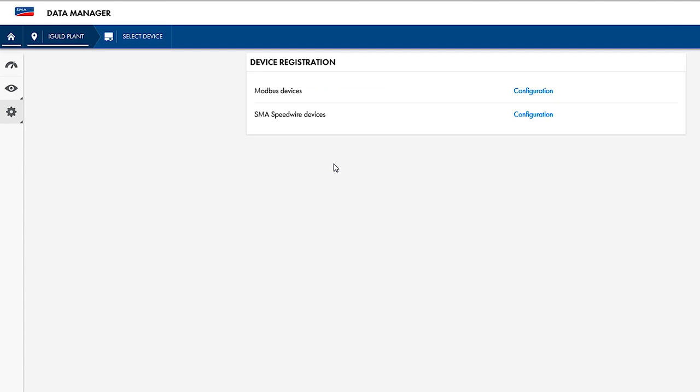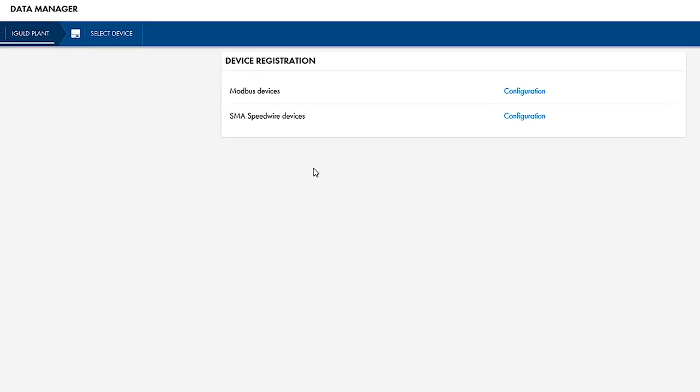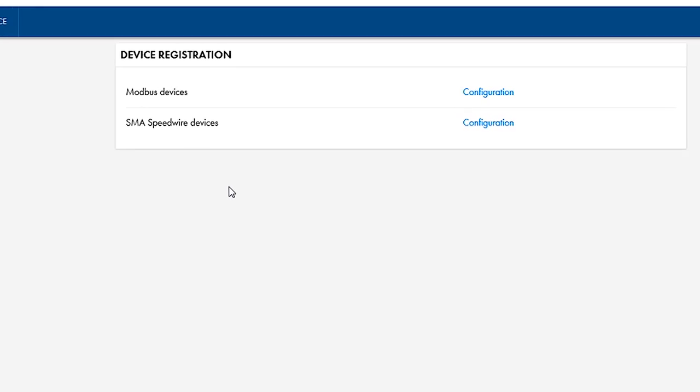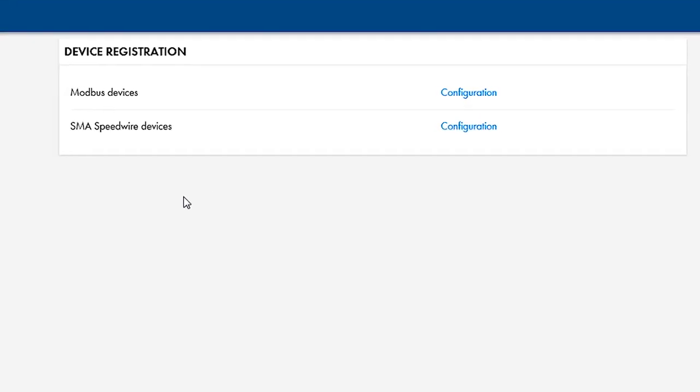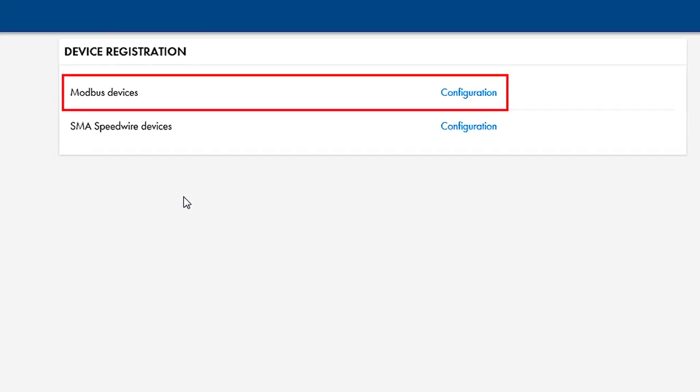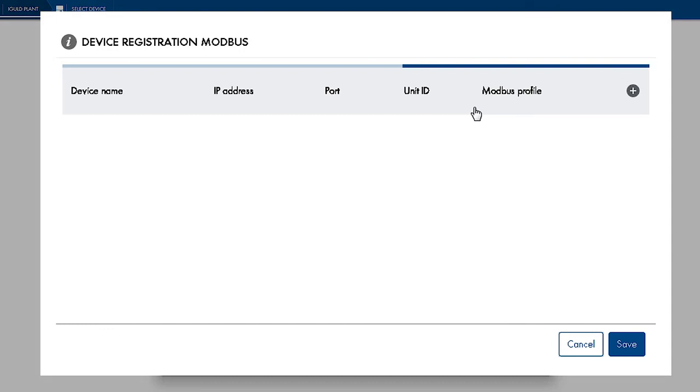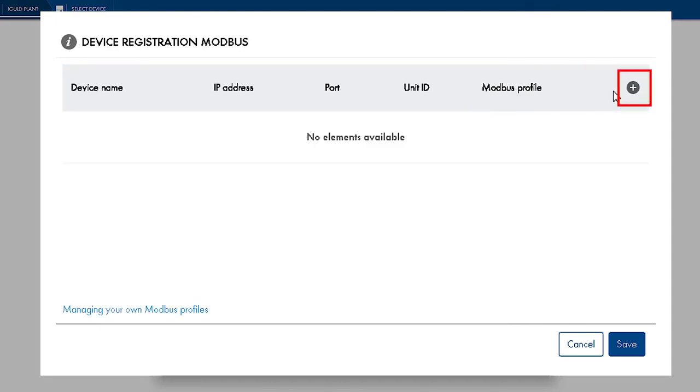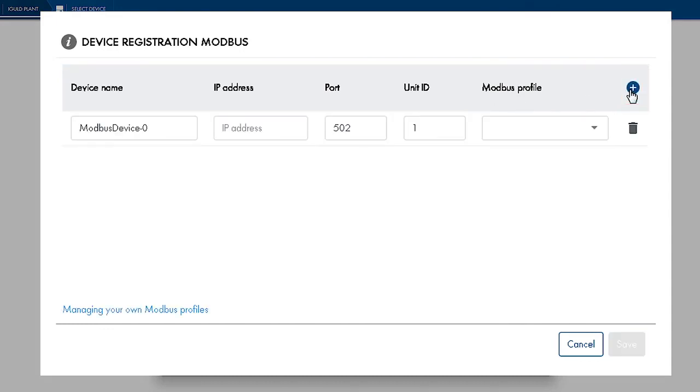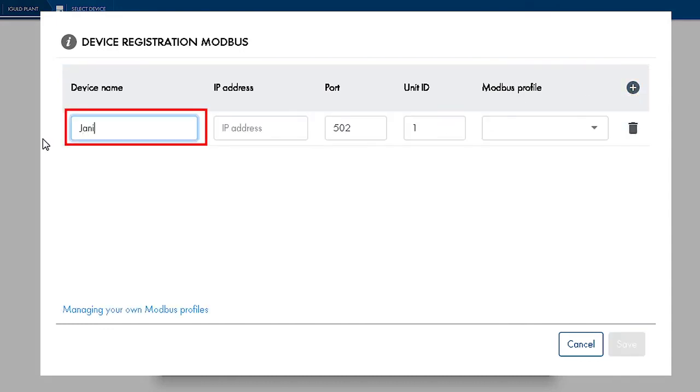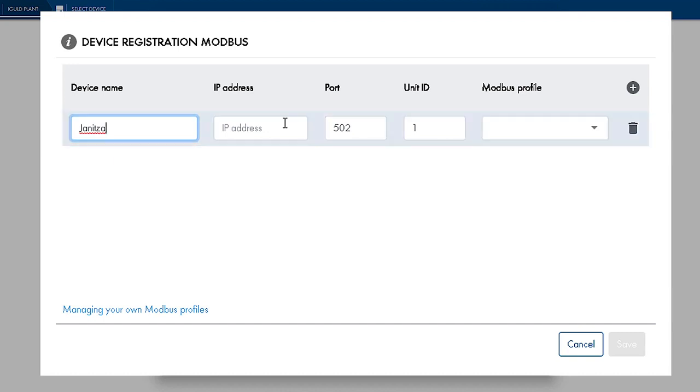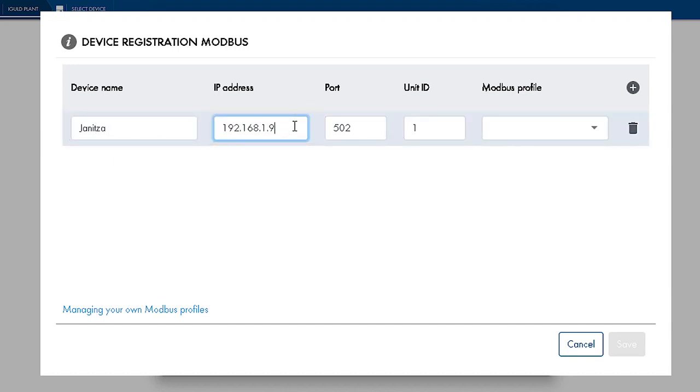A Janitza UMG604 Modbus energy meter can also be set up via the Device Registration menu. To do so, click on Modbus Devices Configuration. Then assign a device name and enter the IP address, port, normally 502, and Unit ID under which the device can be accessed.